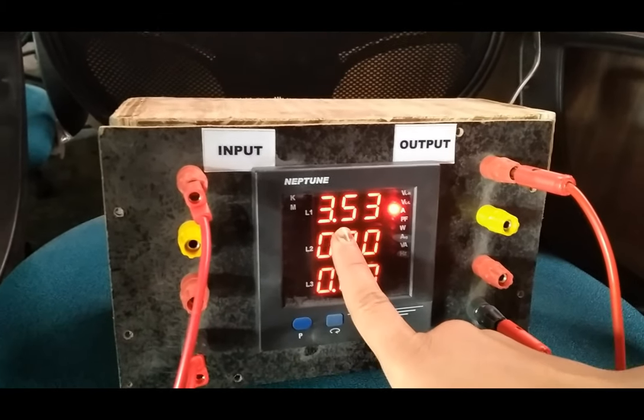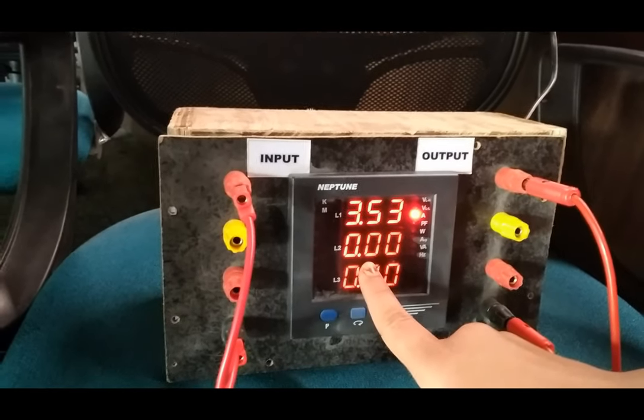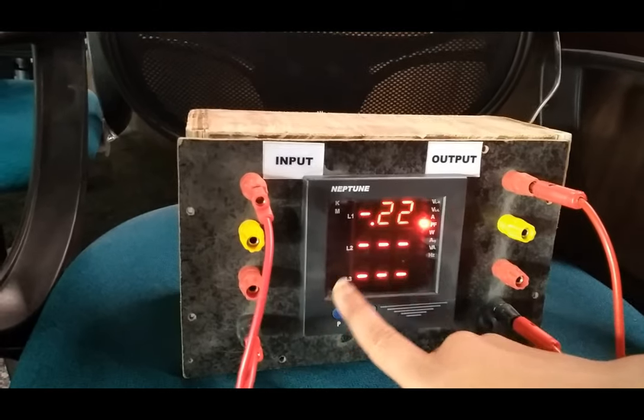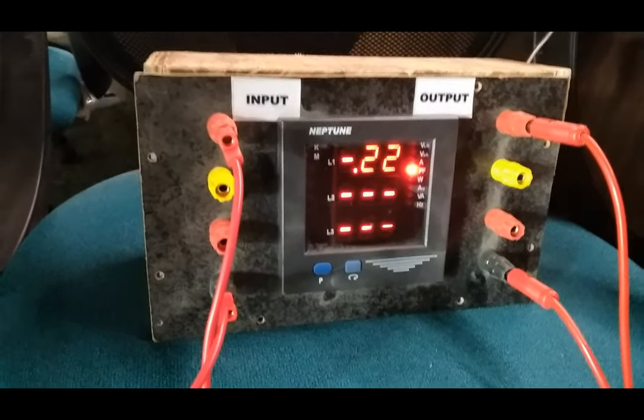The current is shown here as 3.53 A. All other Y and B terminal currents are shown as 0, as we are using only single phase. The power factor is minus 0.22.